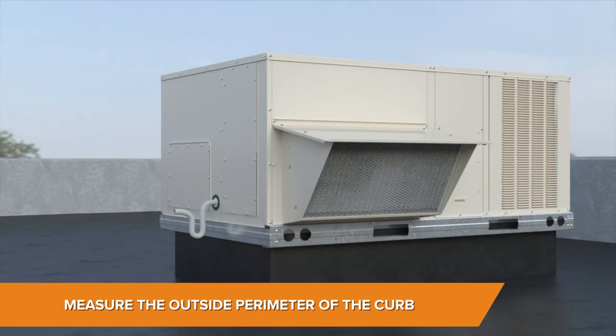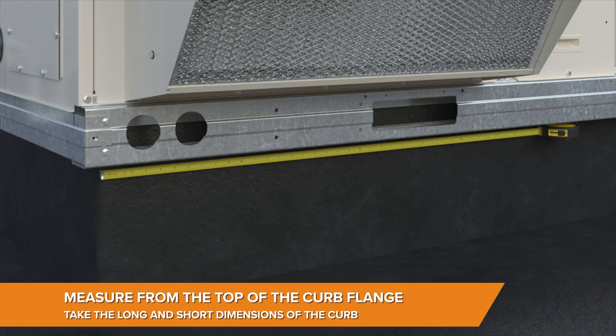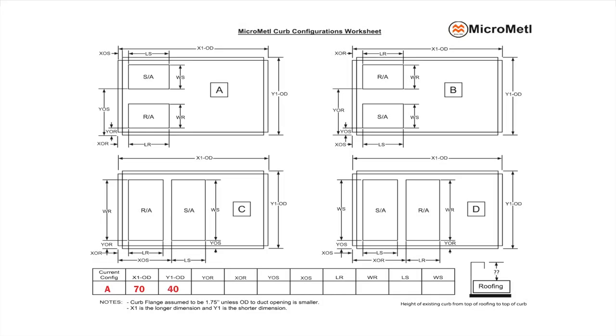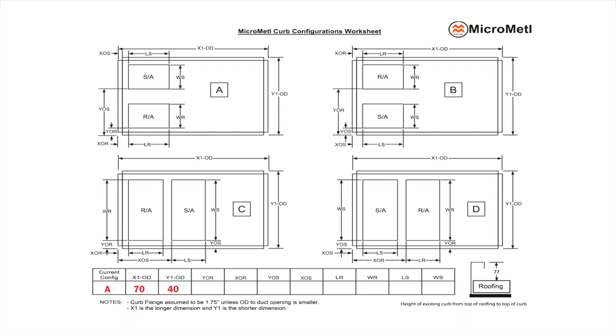Let's start with the measurement of the outside perimeter of the curb. Measure from the top of the curb flange, take the long and short dimension, write the long dimension in X1 and the short dimension in Y1, and don't add to the dimensions. MicroMetl engineers will add an inch and a half overall to every curb adapter.